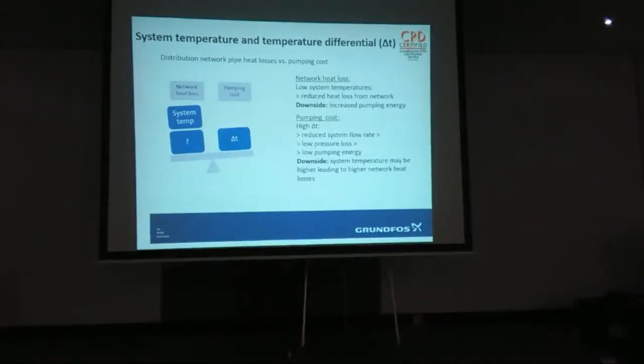What tends to happen is, in the old days, it was an 11-degree drop, did 10 litres a second. Now it's a 20-degree drop, so it should be roughly half the flow rate, and the resistance should come through the floor. What's actually happening with it? That was the system curve working here. Now it's like that. You work up there, because you've got smaller pipe works, and the resistance is gone. If you use the same size pipe work, you work down there, much smaller pipe. If you're digging a hole to bury the pipe, it's the same size hole, usually.